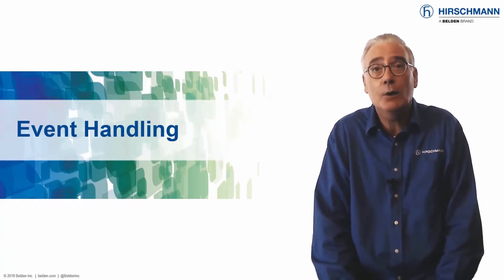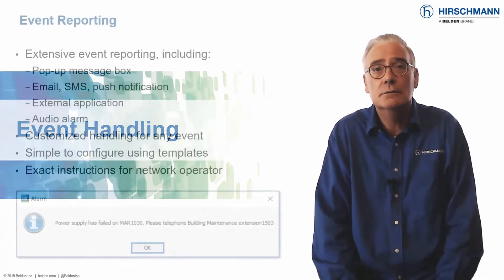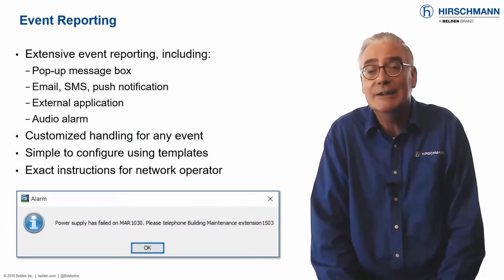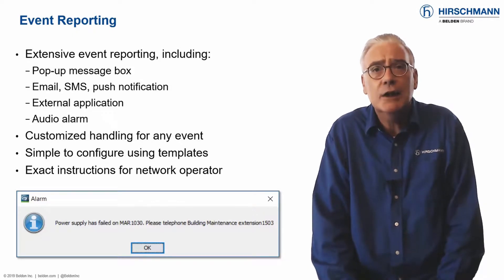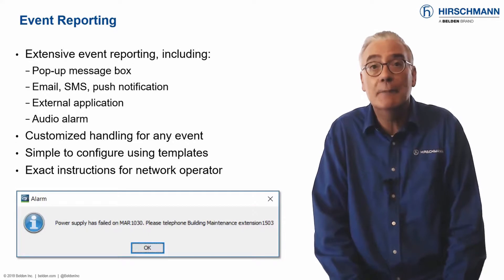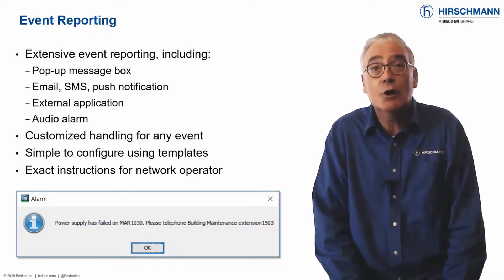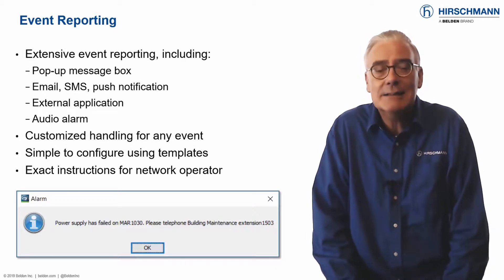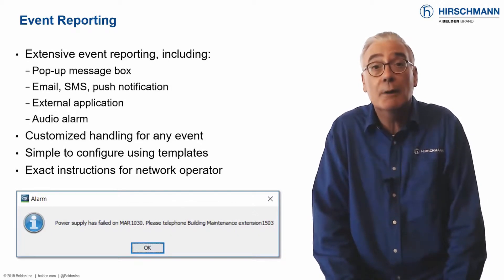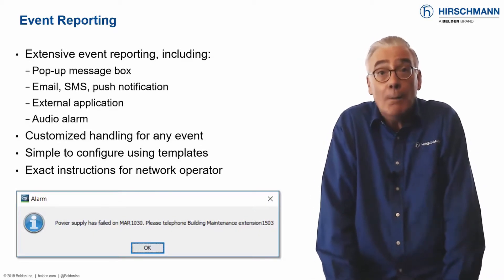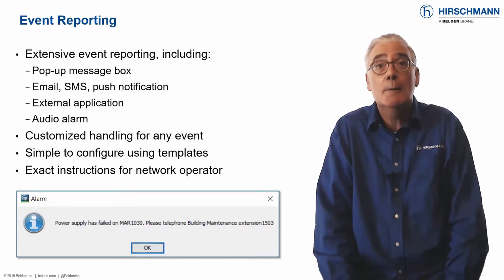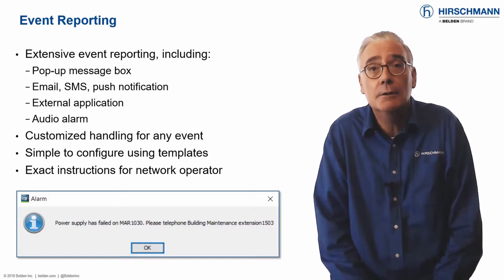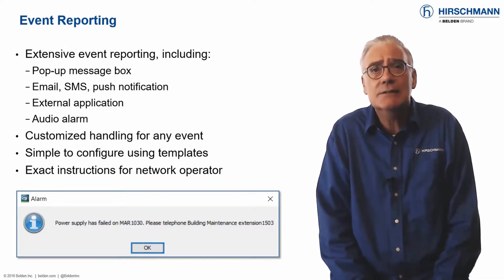Industrial HiVision gives you a choice of how to achieve these objectives. Event logs store information for later use, but often if an event occurs, you or your network operators need to know immediately. Industrial HiVision offers many options for event reporting: an audio alarm will attract attention, standard options like email, SMS and push notifications make use of mobile phones, an event can start any other application, and a pop-up message box can give the operator precise instructions for dealing with the alarm. Event handling can be customized to suit your requirements.